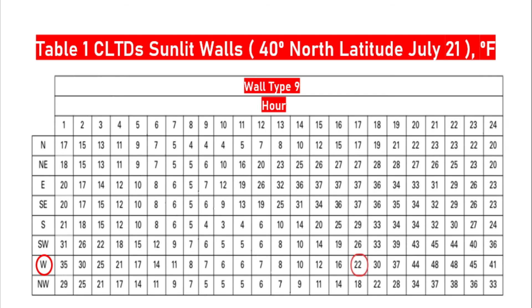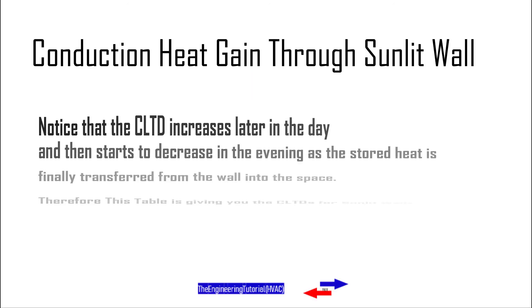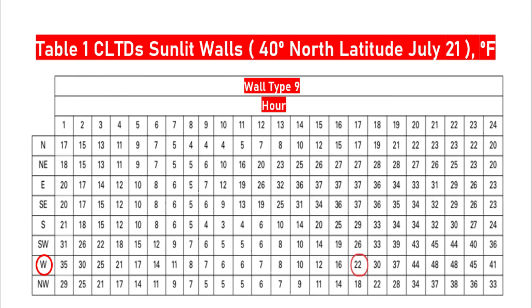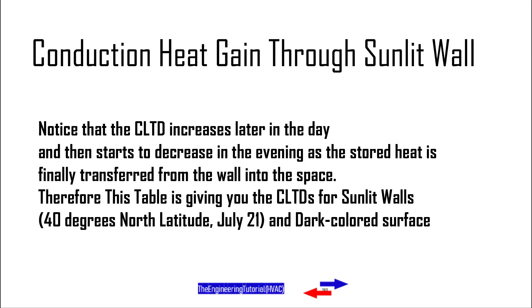A particular table includes CLTD factors for the west-facing wall similar to the type used in our example building. The data in this table are based on the following assumptions: the CLTD increases later in the day and then starts to decrease in the evening as the stored heat is finally transferred from the wall into the space. This table gives CLTDs for sunlit walls at 40 degrees north latitude, July 21st, and dark-colored surface.